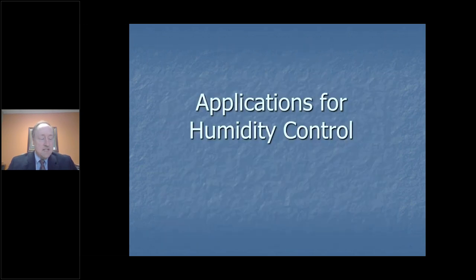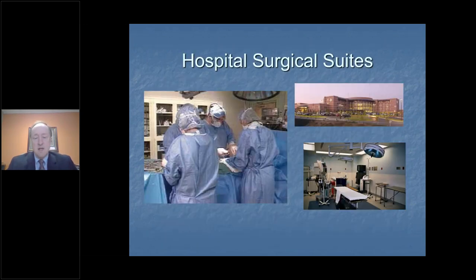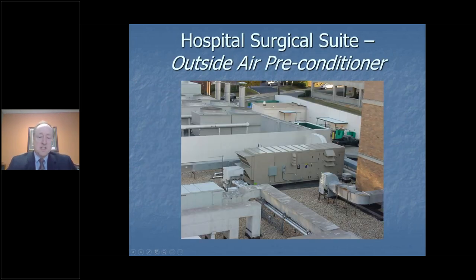And then for the last 2 to 3 minutes, we're going to show you very briefly some hospital applications. This was up on the rooftop of a unit. This is just a chase where the outside air would come in. You'll see on the next schematic, this air would be drawn into some louvers on the side of the building. The whole purpose of this wall was just to keep all the diesel fumes from the delivery trucks out of the intakes. In this case, one of those louvers fed the surgery suite, and we added a desiccant dehumidification system on the roof. We used pre-cooling coils, desiccant, and post-heating and post-cooling coils. And this is duct that goes into the side of this.